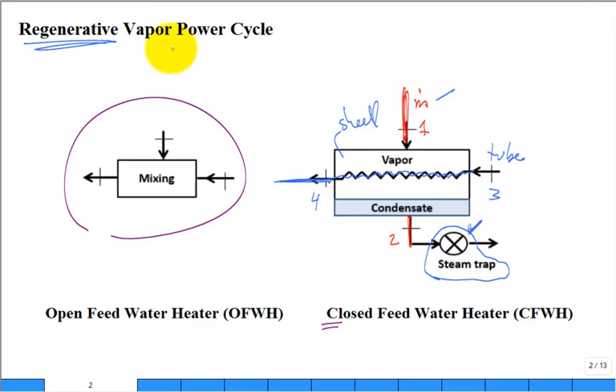What's it doing? It's basically monitoring the condensate level. If the condensate level gets too high, it opens up and lets condensate flow through it. Can you tell by the little X right there what it really is? A valve, a throttling valve, exactly. But it's not always open, and if all the condensate would go through and the steam says 'hey, I'm next, let me go through,' the valve closes. It traps back the steam, won't let the steam go through, only condensate. No vapor through, only liquid.